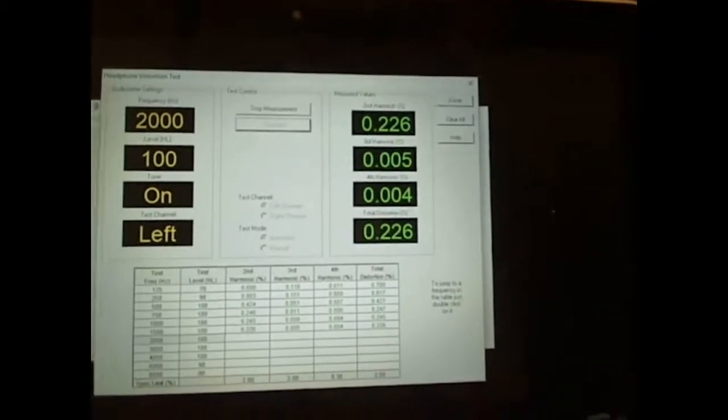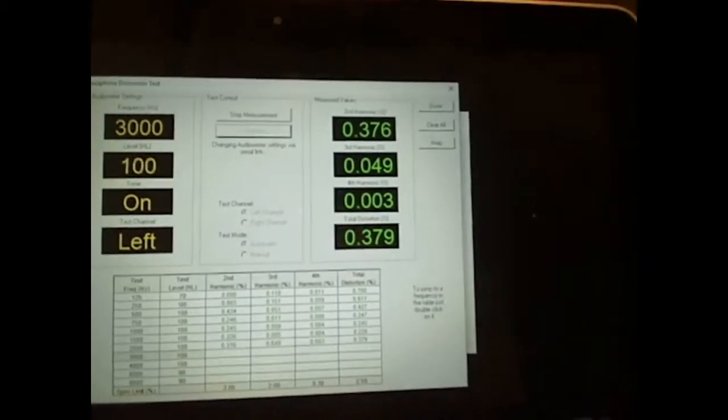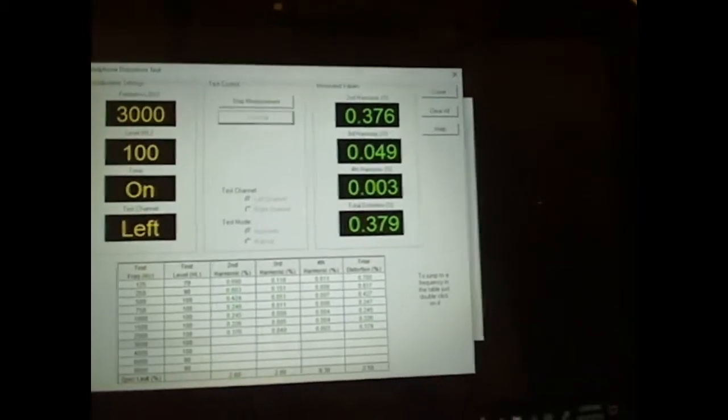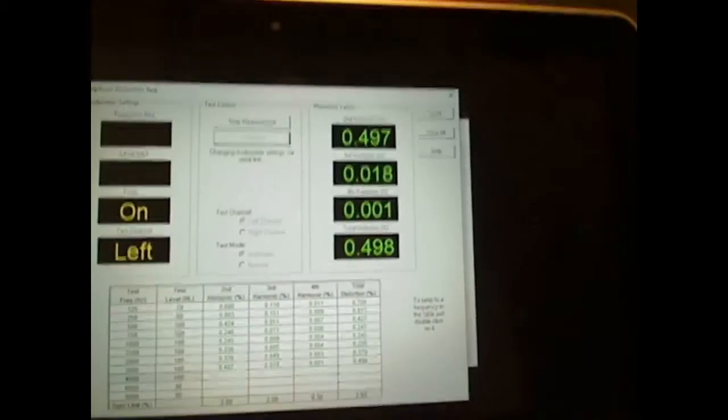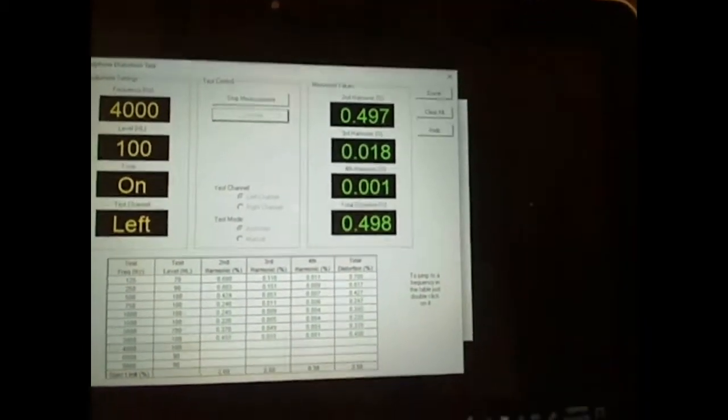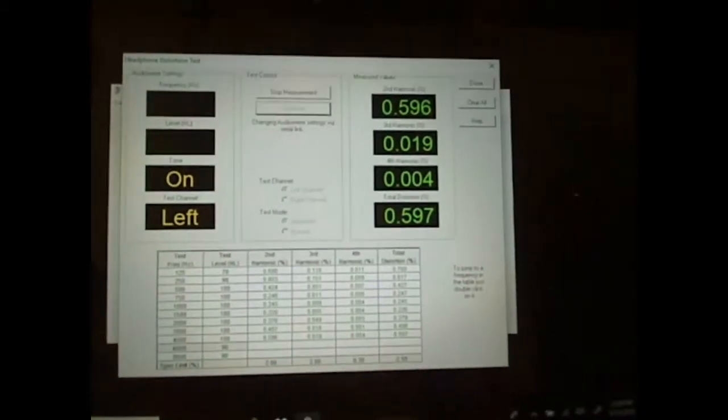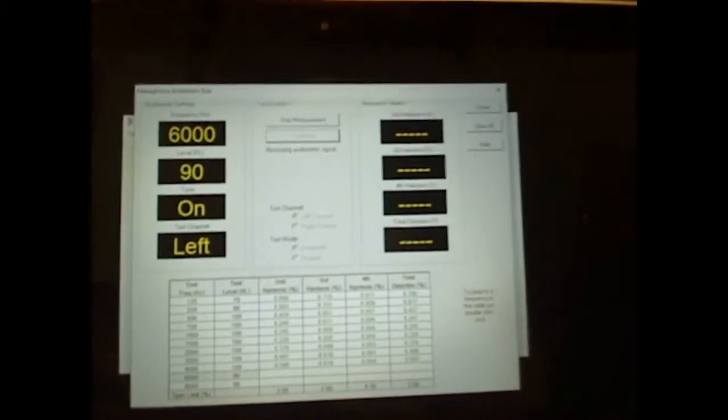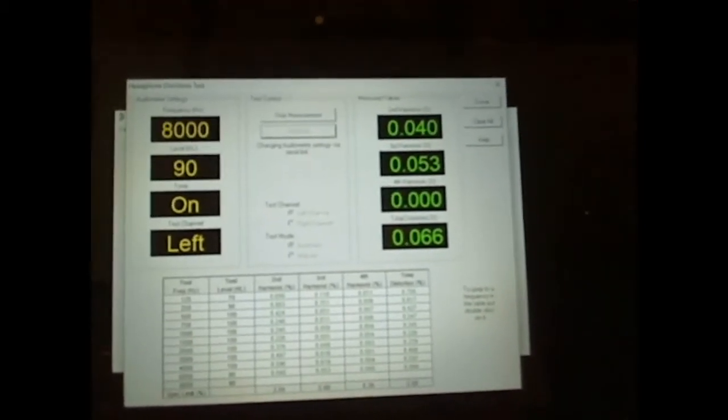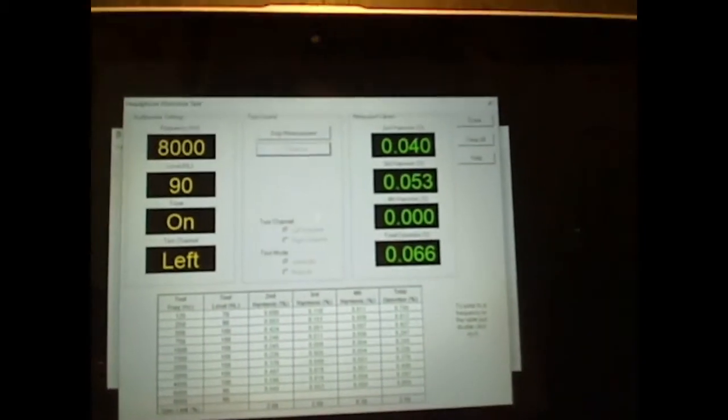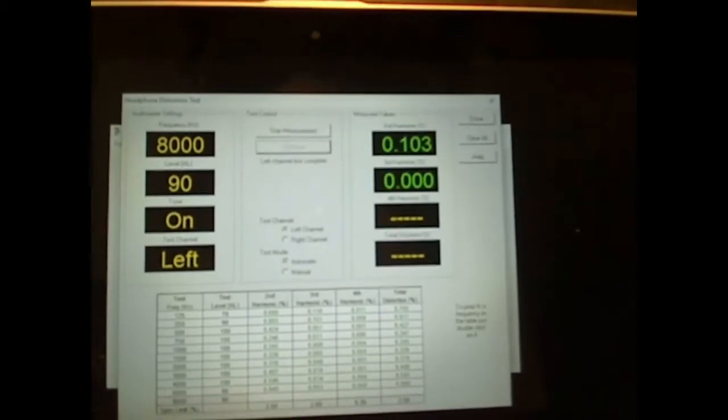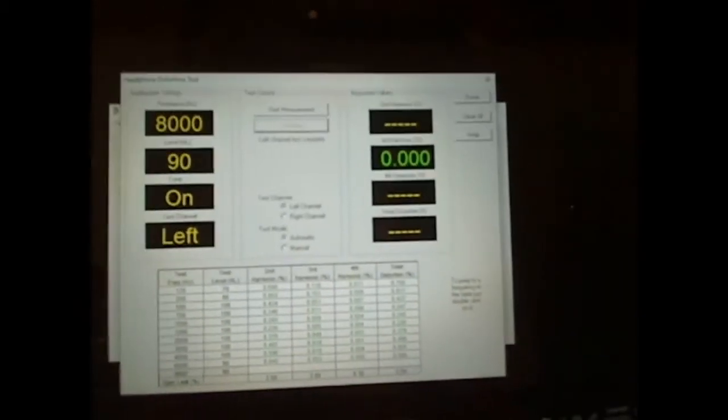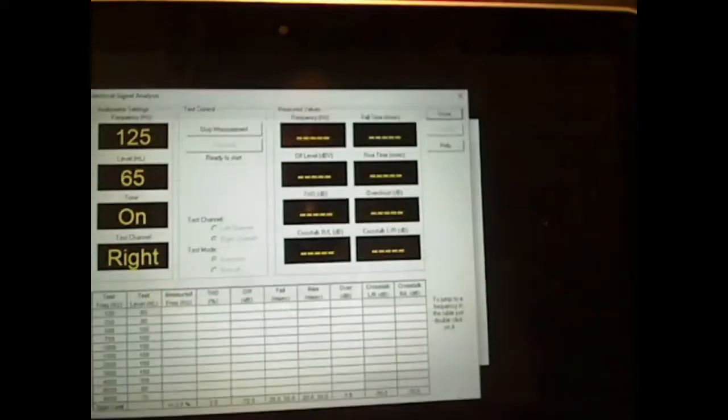There is nothing left to chance. We put no OKs, no check marks, no nothing on a calibration sheet. If you have a calibration sheet with an OK on it, more than likely it wasn't done. If I know it's OK, I must have seen a number in order to be able to find out what that OK is. Well, it's a lot less problem just to write down the number than it is to write OK.